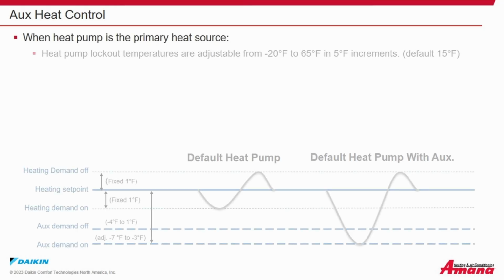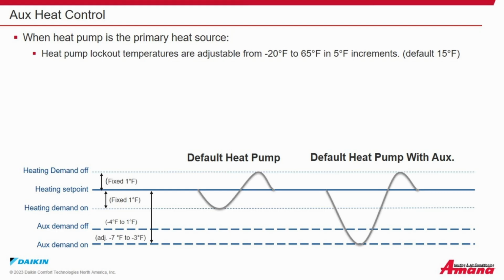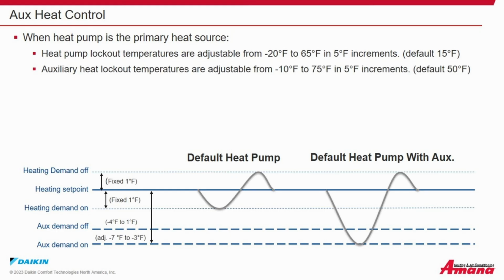Auxiliary heat control. When the heat pump is a primary heat source, the heat pump lockout temperatures are adjustable from -20 degrees to 65 degrees Fahrenheit in 5 degree Fahrenheit increments. Default is 15 degrees Fahrenheit. Auxiliary heat lockout temperatures are adjustable from -10 degrees to 75 degrees Fahrenheit in 5 degree increments. Default is 50 degrees. Auxiliary heat demand.